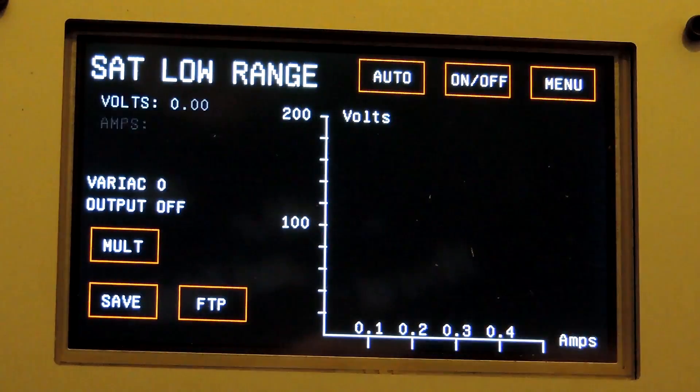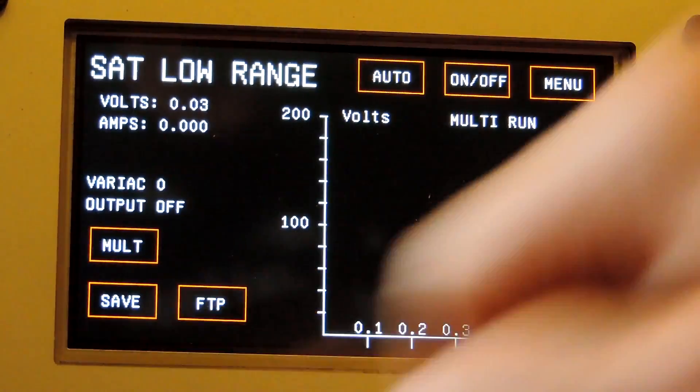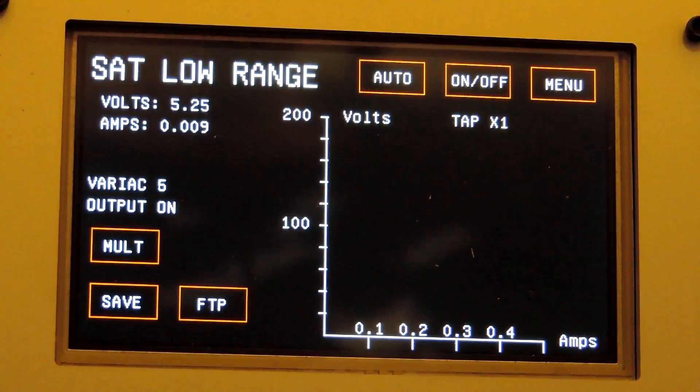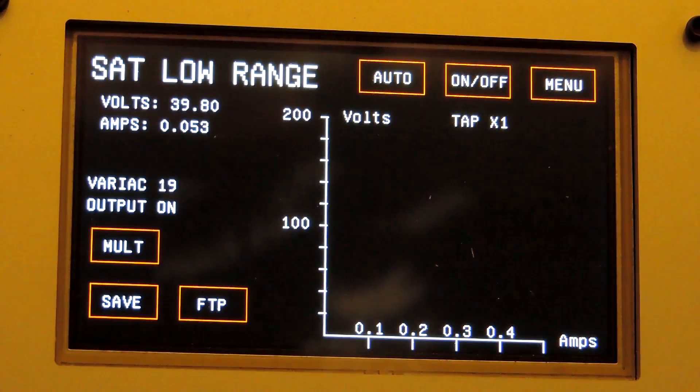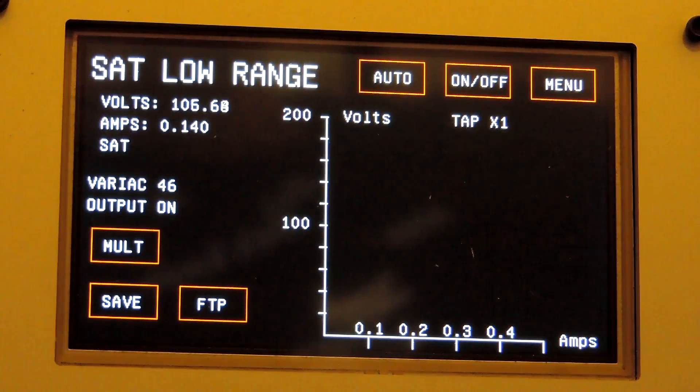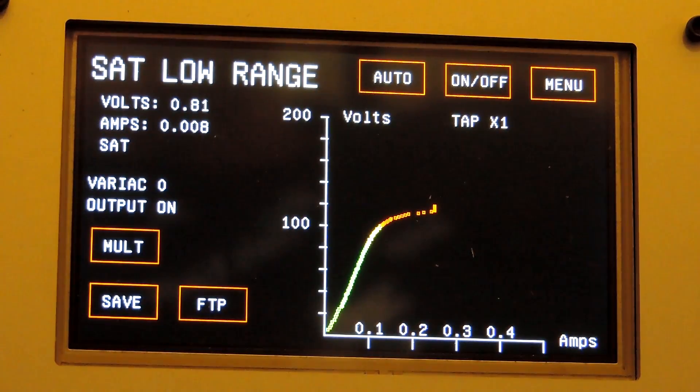And multi. It is now running the test on tap X1. The LED is red because the red jack is connected. When it reaches the saturation point, under the word amps, the word sat will appear. The test for that tap is complete. It is running the variac down and plotting the graph.